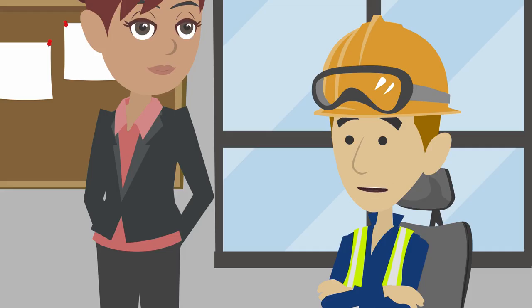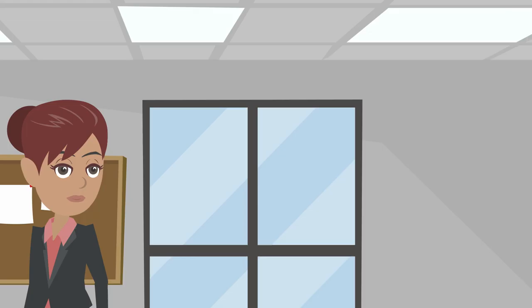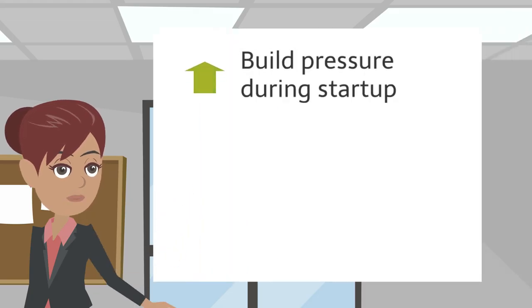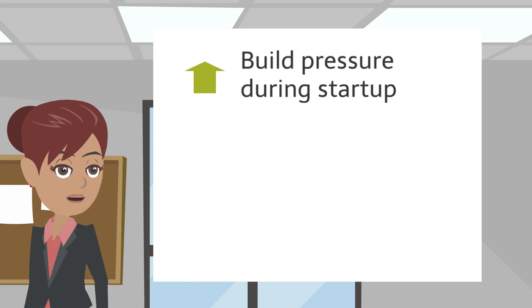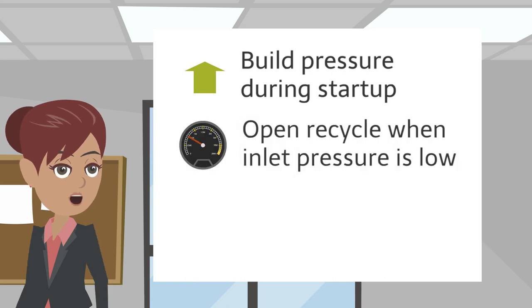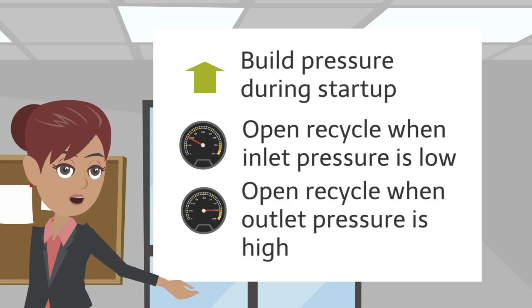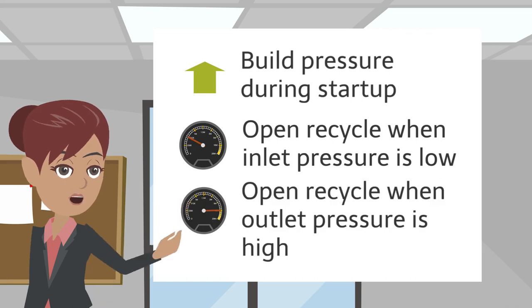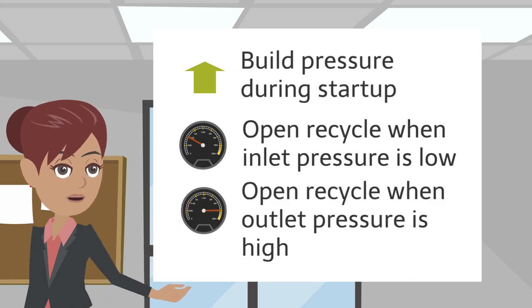Why do we have a recycle line if opening it will overpressure the inlet side? The recycle line is important for starting up a compressor to build up operating pressures. It is also used to control fluctuations in pressure by opening when the compressor inlet pressure is too low or outlet pressure is too high. The compressor will not overpressure if the recycle valve opens and there is still a flow path through the compressor.